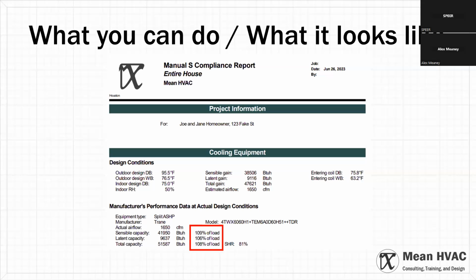If you're in a high humidity climate, latent capacity is the most important factor. Second most important, by a narrow margin, is not having too much sensible. In an ultra dry climate, there's no good reason to undersize cooling equipment, because the negative consequences of being slightly oversized there are negligible.